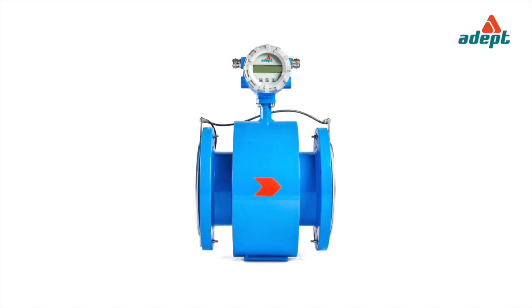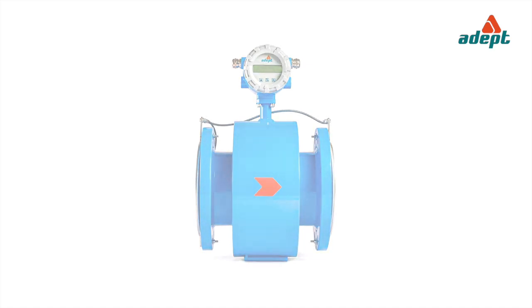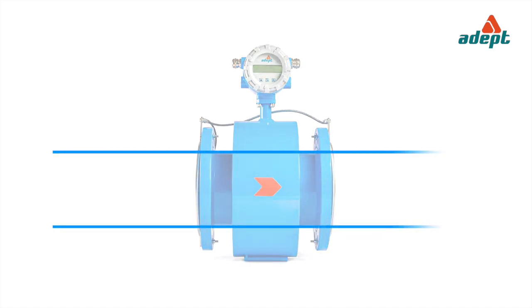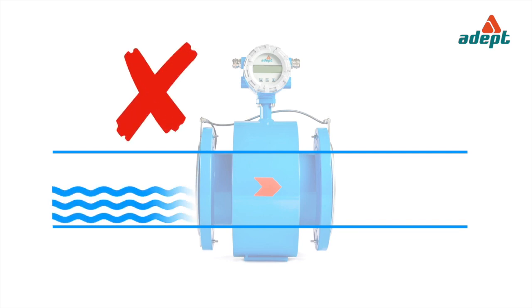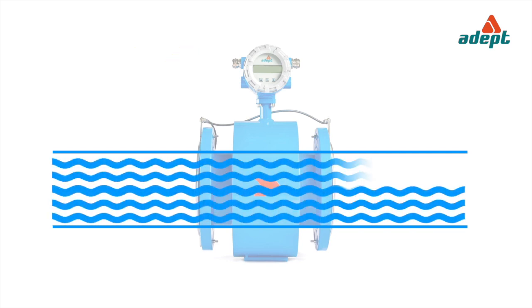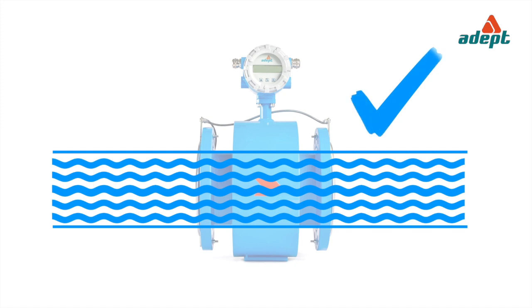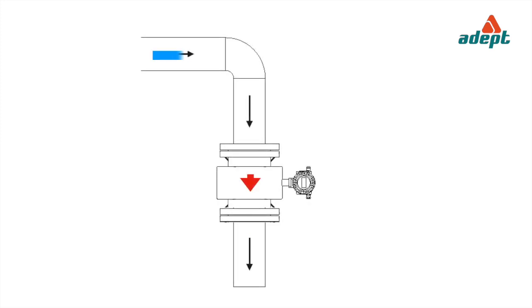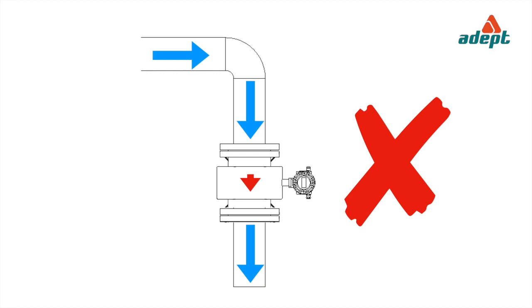Don'ts. Never install the flow tube such that it will remain empty. Even partial flow should be avoided. Pipeline layout should be modified in such a way that the flow tube will always remain in the full flow condition with water. Never install the flow tube in vertical pipelines with the liquid flow in the downward direction.